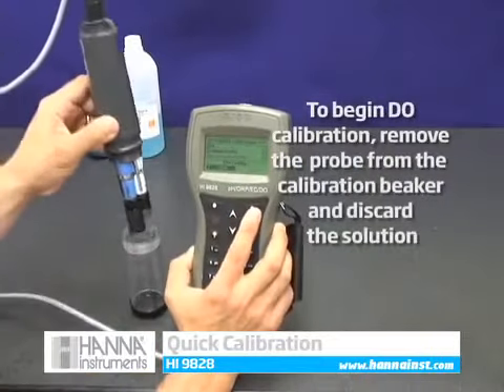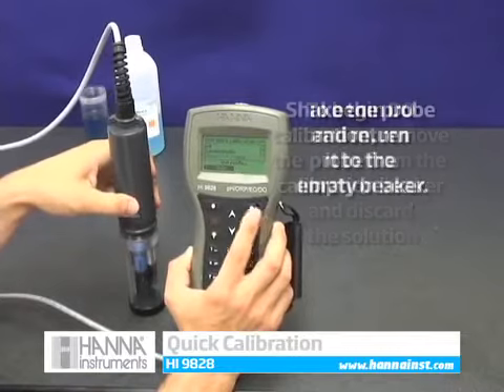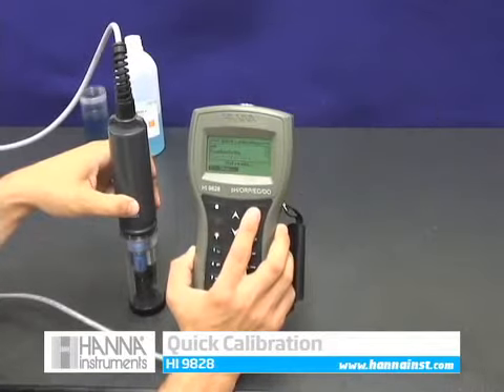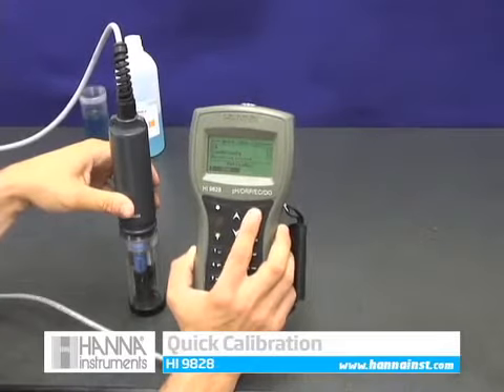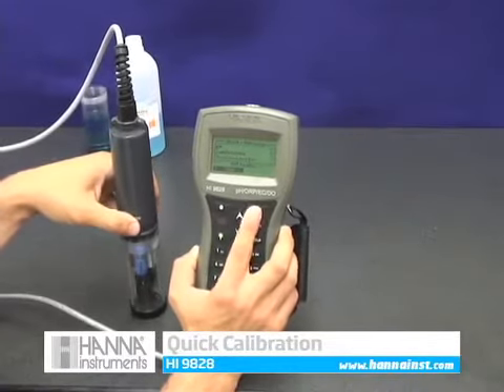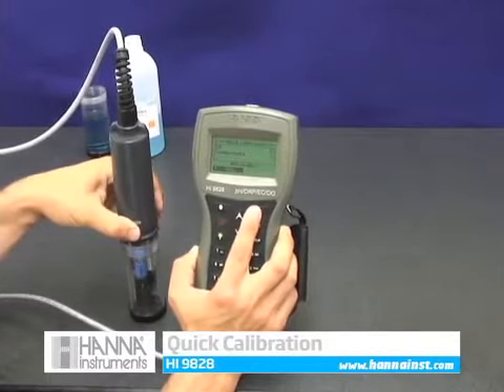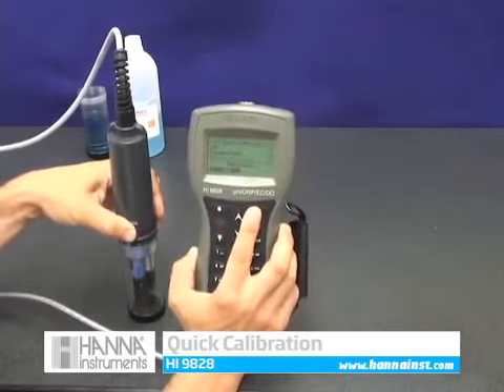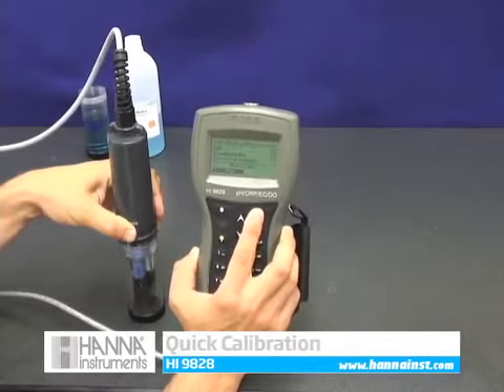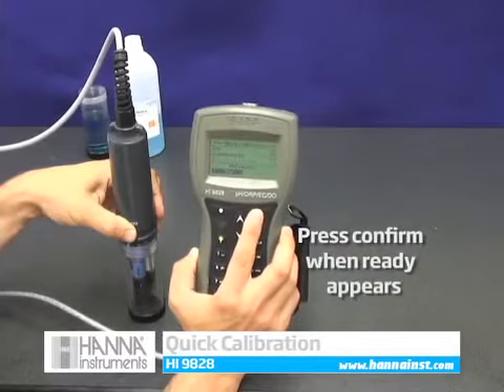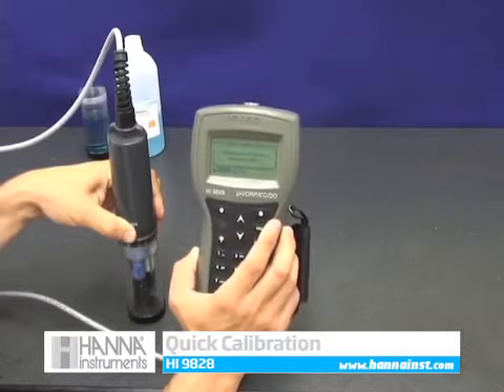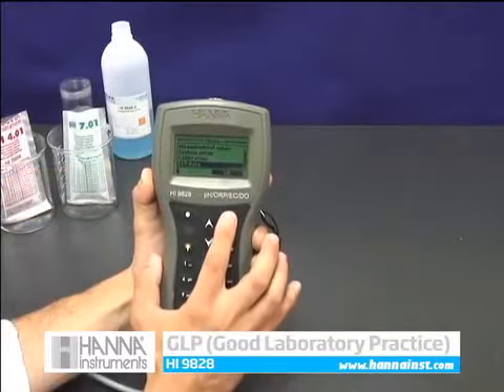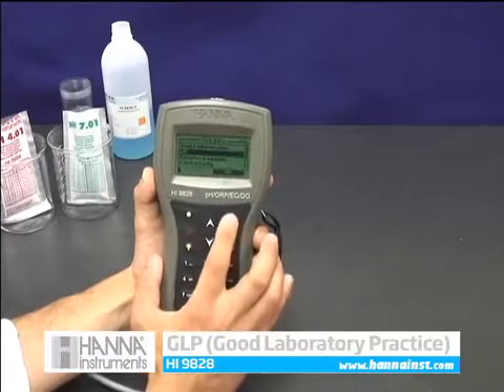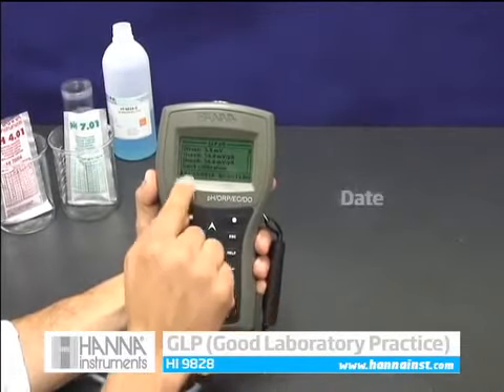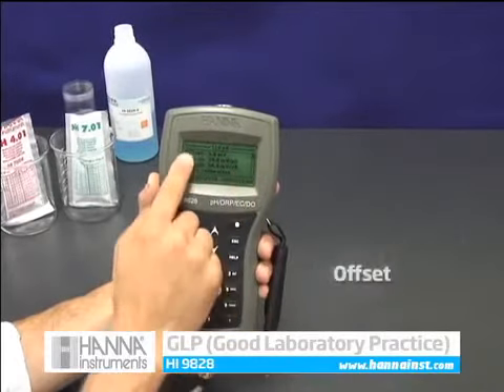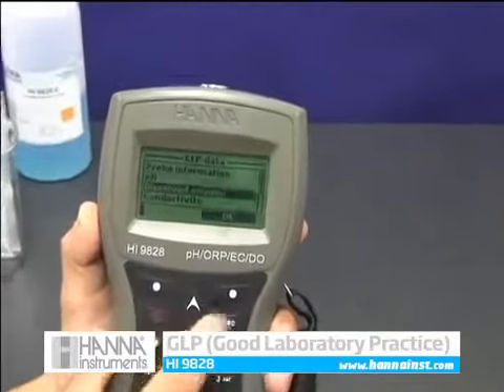For dissolved oxygen calibration, remove the probe from the beaker and discard the solution. Shake the probe and reinsert it into the beaker and proceed with calibration as normal. After confirming the DO calibration, the meter will now be calibrated to all sensors. GLP lets you determine when the last time calibration was performed. GLP shows the date, time, slope, and offset for calibration performed on your pH, conductivity, and DO sensor.